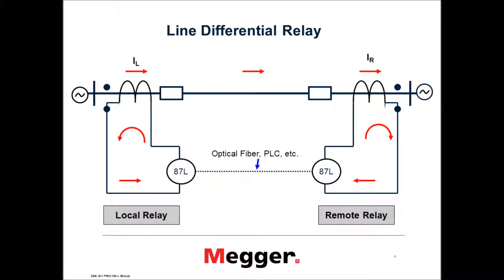I'm going to focus primarily on line differentials. It's fairly simple to understand and very fast. The line differential is still today the highest speed, most secure means of line protection. Typically, as we all know, it's current in equals current out. In this case, I'll show an optical fiber communication link between the two ends of the transmission line. When the fault is internal, it operates very quickly and very securely, and when the fault is external, it will not operate.